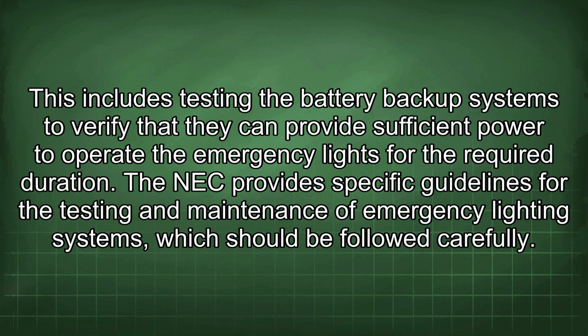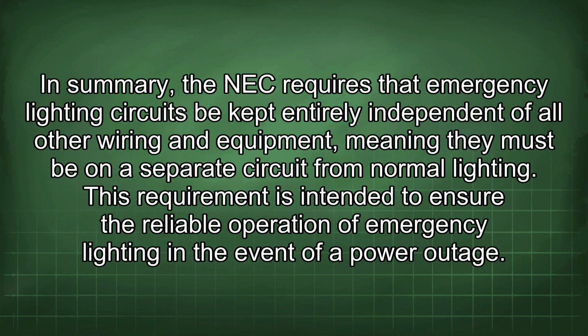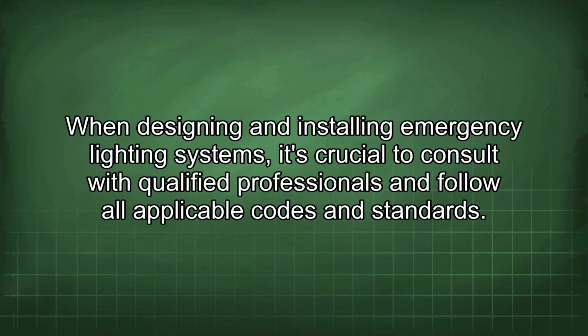In summary, the NEC requires that emergency lighting circuits be kept entirely independent of all other wiring and equipment, meaning they must be on a separate circuit from normal lighting. This requirement is intended to ensure the reliable operation of emergency lighting in the event of a power outage. When designing and installing emergency lighting systems, it's crucial to consult with qualified professionals and follow all applicable codes and standards.